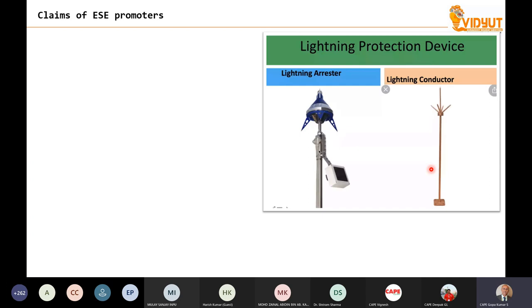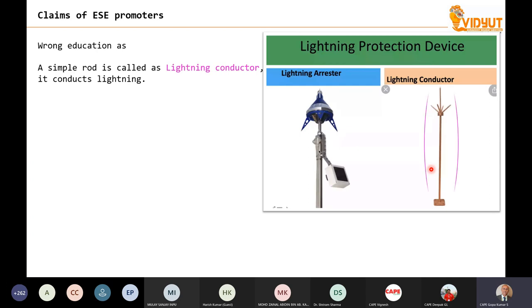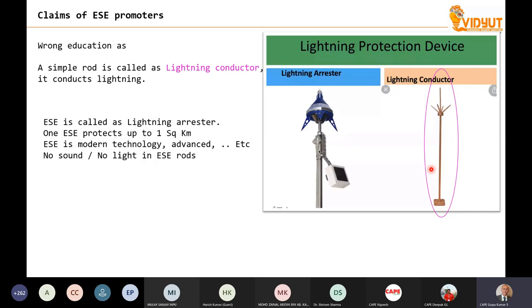There are two technologies available. One is called the lightning conductor, which is as per the Indian standard or the National Building Code of India. It conducts the lightning, very simple. The second one is called early streamer emission, which is called a lightning arrestor. So the first one is the lightning conductor and the second one is the lightning arrestor. One lightning arrestor protects up to 1 square kilometer.